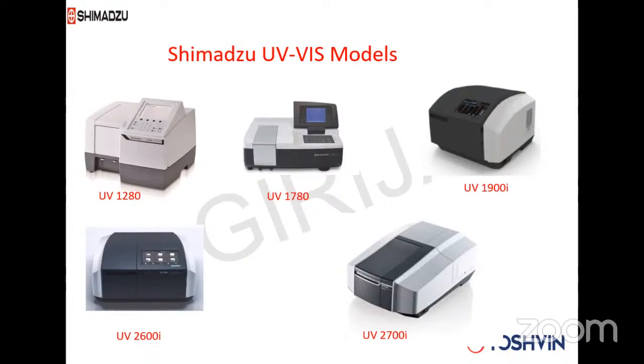2700 is also a research model. It contains two monochromators inside. All other instruments contain only one monochromator, but 2700 contains two monochromators because we want to reduce the stray light. In 2700, the stray light specification is 0.00001%. We are able to achieve that level because of two monochromators. But the instrument becomes very expensive, and it's only promoted for research activities. For routine applications in the pharmaceutical industry, 1900 is an undisputed model, 1900I.